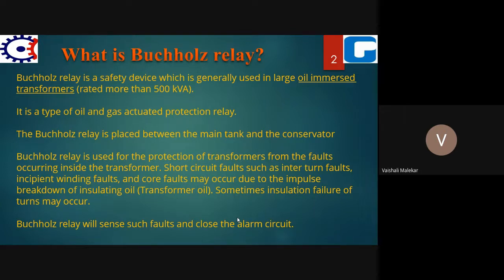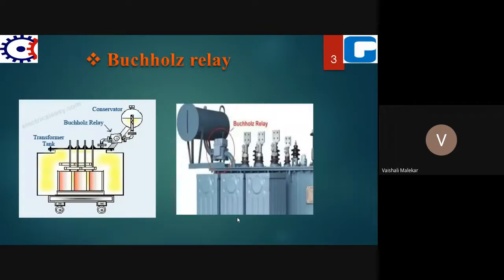The Buchholz relay will sense such faults and give the alarm signal. Means it will close the alarm circuit so that the alarm sounds, and the circuit gets disconnected. The transformer will get disconnected from the main circuit. See here where this Buchholz relay is placed. It is placed in between the transformer tank and the conservator. You can see in both diagrams, the transformer tank is there, the conservator is there, and the Buchholz relay is placed in between the conservator and the transformer tank.